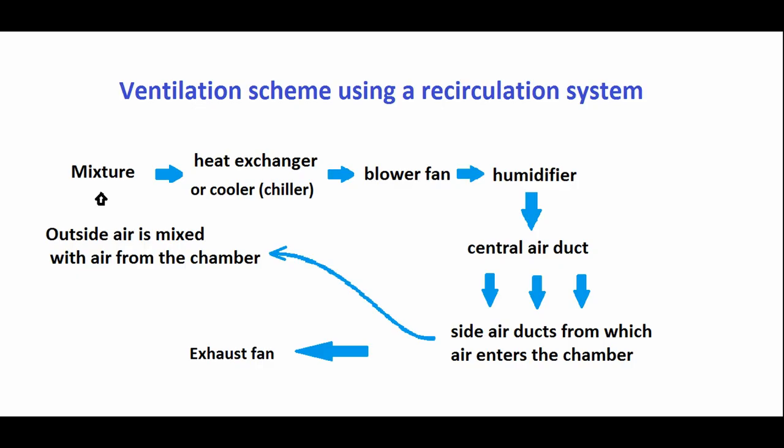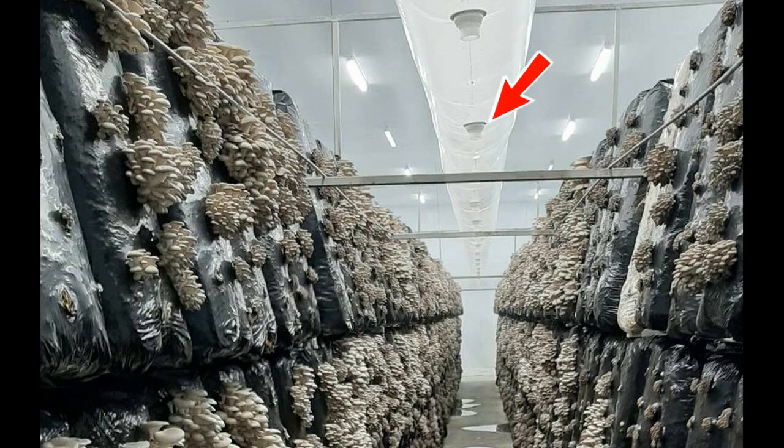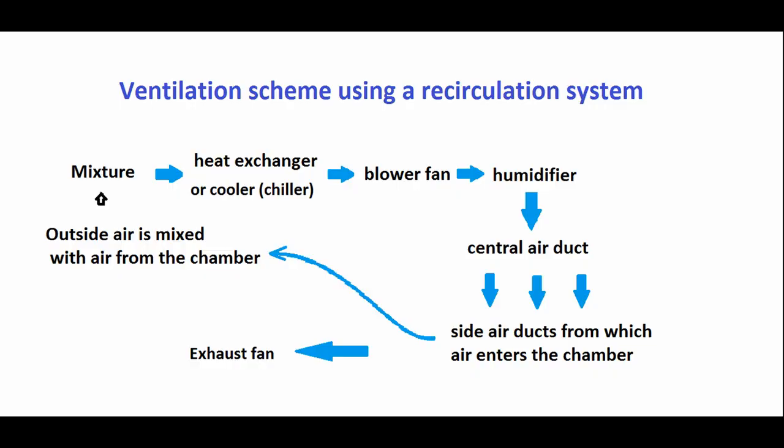Side air ducts diverge from the central air duct. These air ducts have nozzle cups. Through them, air blows into the floor and takes carbon dioxide and moisture from the mushrooms. Then part of the air flow is returned to the recirculation system. The second part of the flow is brought out by the axial fan of the hood. The amount of air that comes out through the hood should be equal to the amount of air that came in from the street.